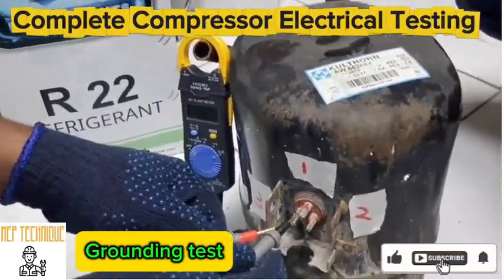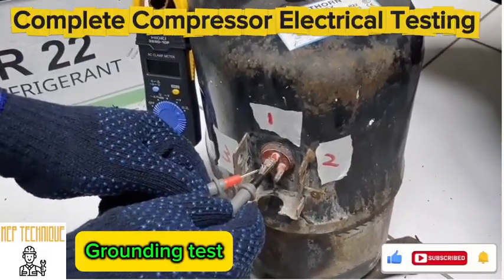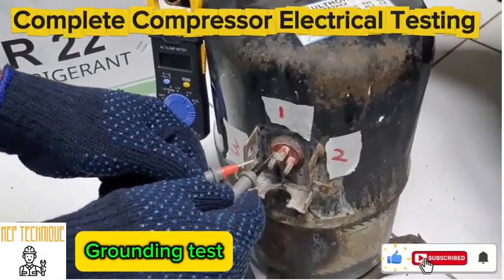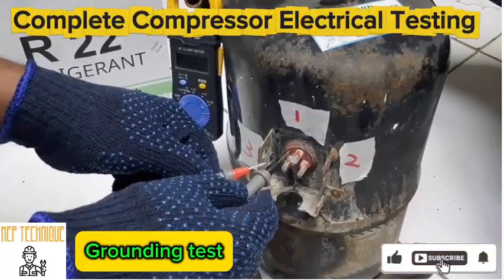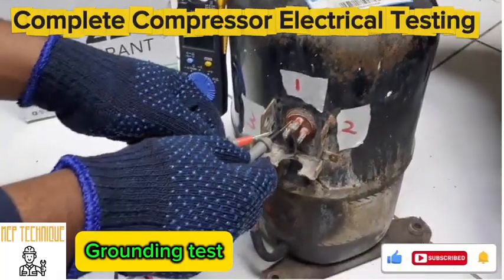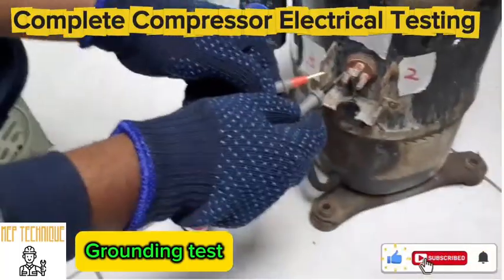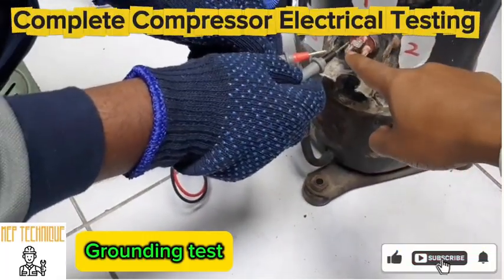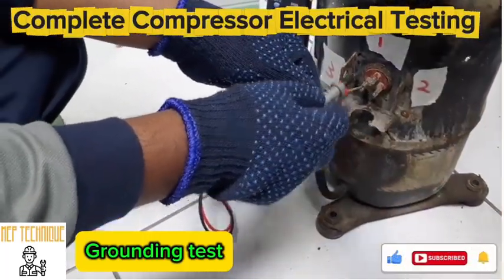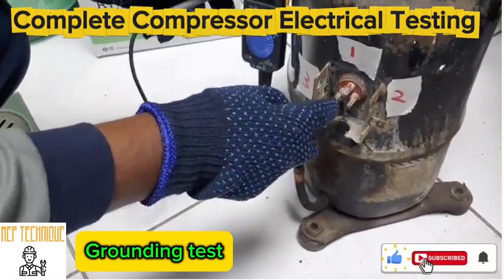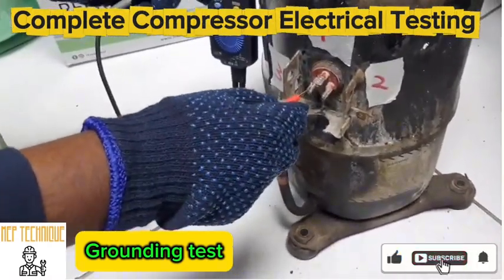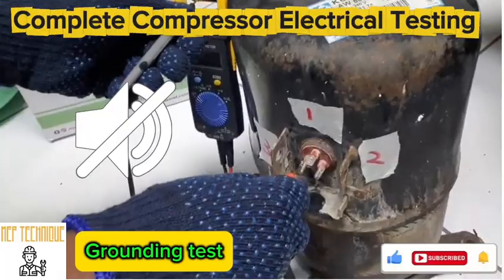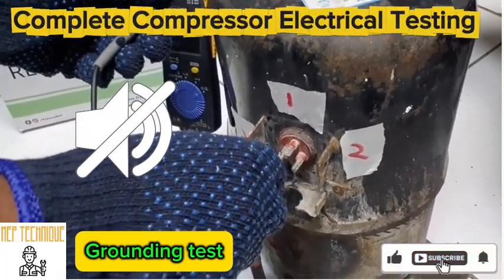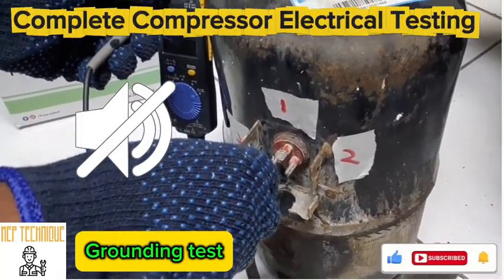Now we are going to check the ground with the clamp meter, but it is not recommended to check the ground with a clamp meter. Why, I will show you. First, connect one lead to one terminal and the other to the body. You can see there is no continuity, right? So no ground fault was found with the clamp meter, but this is not an accurate method to check grounding.